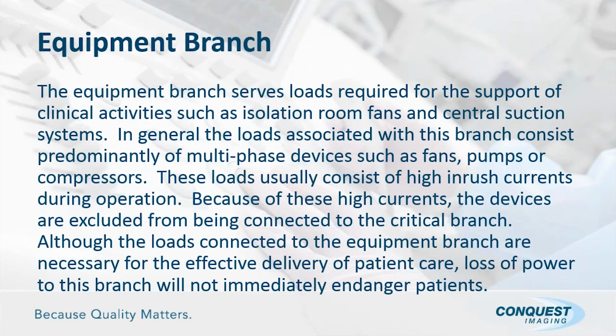The equipment branch serves loads required for the support of clinical activities such as isolation room fans and central suction systems. In general, the loads associated with these are much higher as far as current load, and they have high inrush currents during operation, and because of these high currents the devices are excluded from being connected on a critical branch. So you can't have this equipment branch associated with the critical branch. The loads connected to the equipment branch are necessary for the effective delivery of patient care, so loss of power to this branch will not immediately endanger patients, but it's still necessary to have this backup.